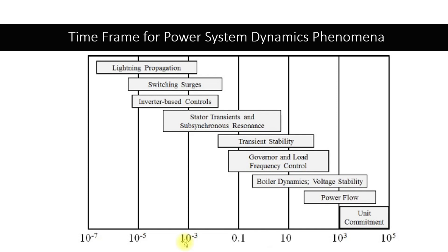There is another kind of study for fast phenomena such as lightning, surges, wave fronts, inverter control, or power electronic circuitry. These are covered by EMTP studies. In EMTP studies, we are talking about nanoseconds to milliseconds — controls which take very short time to operate.